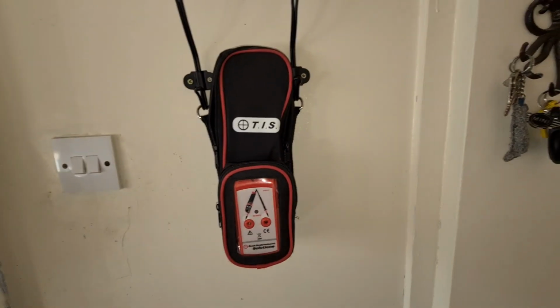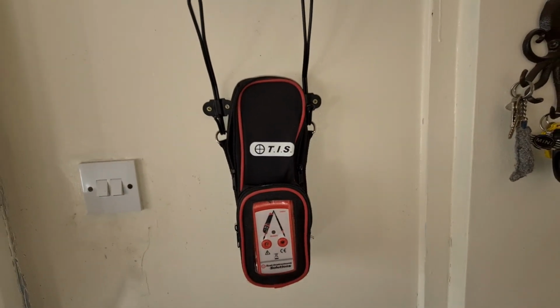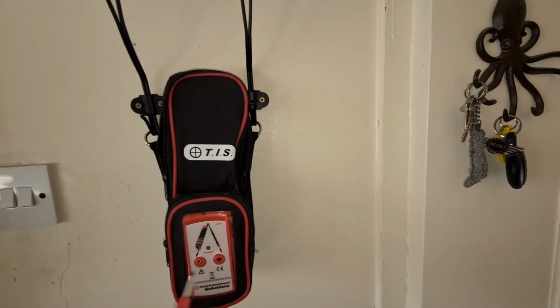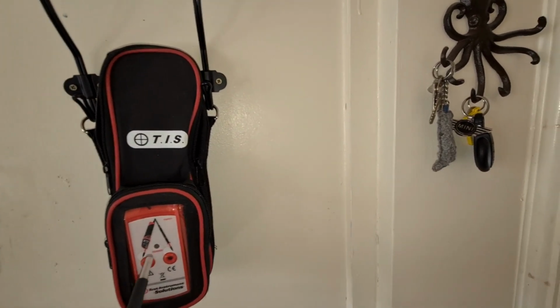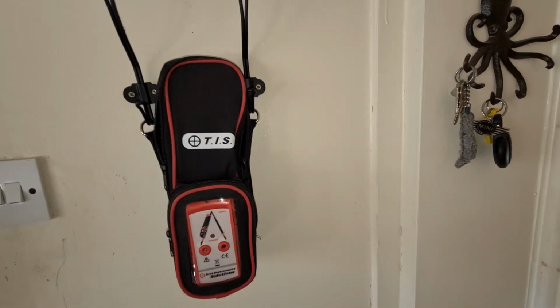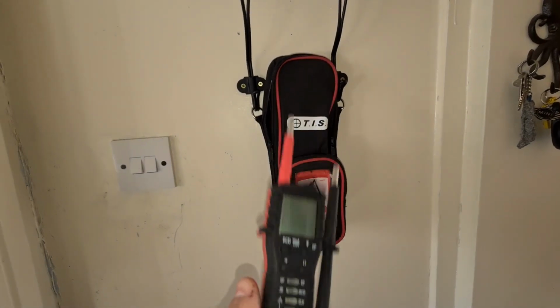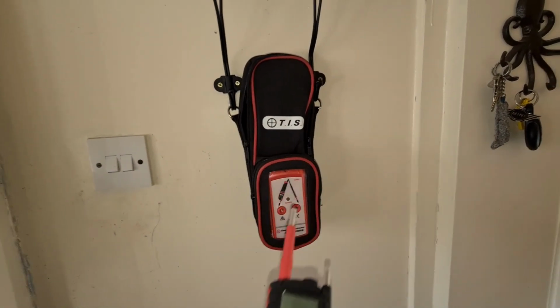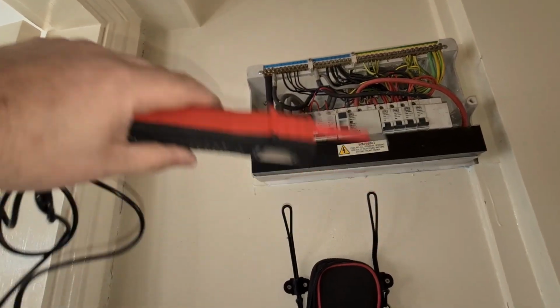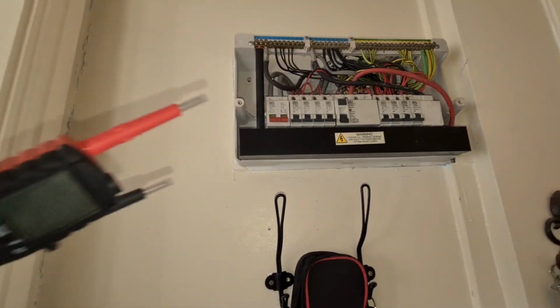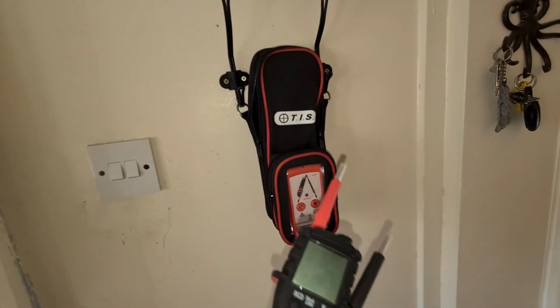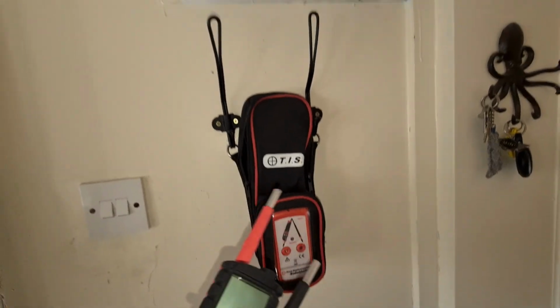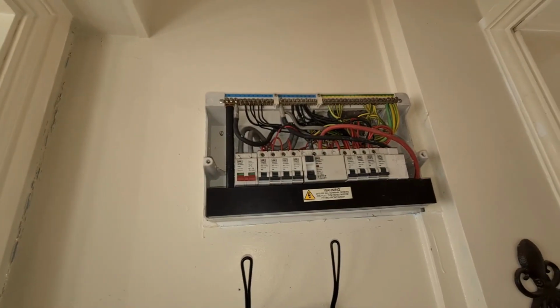I have shared little guides in the past. I won't be doing that kind of thing anymore. I just don't think that's a sensible thing to do. But in essence, you need to prove that your tool works. So you've got your proving unit there. Get the tool in and make sure your voltage indicators are actually working, and then make sure you measure between your lines and your neutrals, your lines and your earths, and then make sure that your voltage indicator is working at the end of all of that as well, and then you know you're perfectly safe inside this board.